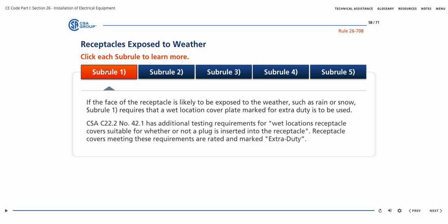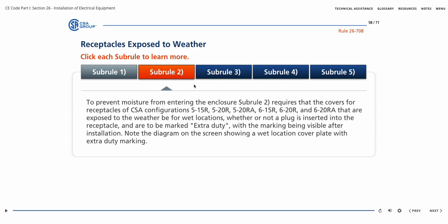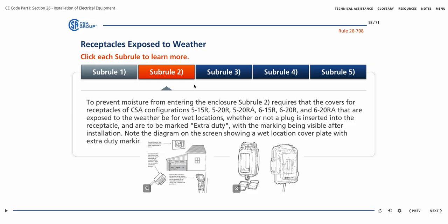CSA C22.2, number 42.1, has additional testing requirements for wet locations receptacle covers suitable for whether or not a plug is inserted into the receptacle. Receptacle covers meeting these requirements are rated and marked extra duty. To prevent moisture from entering the enclosure, Subrule 2 requires that the covers for receptacles of CSA configurations 5-15R, 5-20R, 5-20RA, 6-15R, 6-20R, and 6-20RA that are exposed to the weather be for wet locations, whether or not the plug is inserted into the receptacle, and are to be marked extra duty, with the marking being visible after installation. Note the diagram on the screen showing a wet location cover plate with extra duty marking.